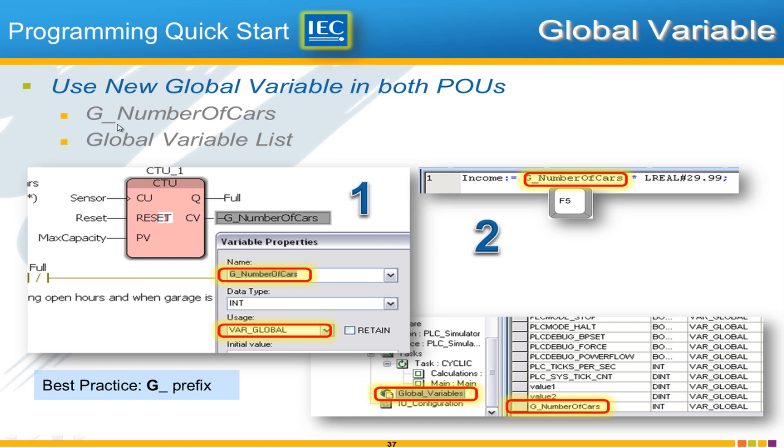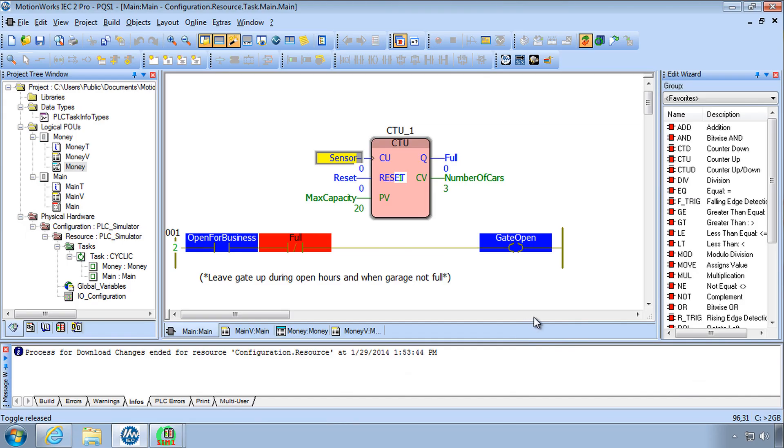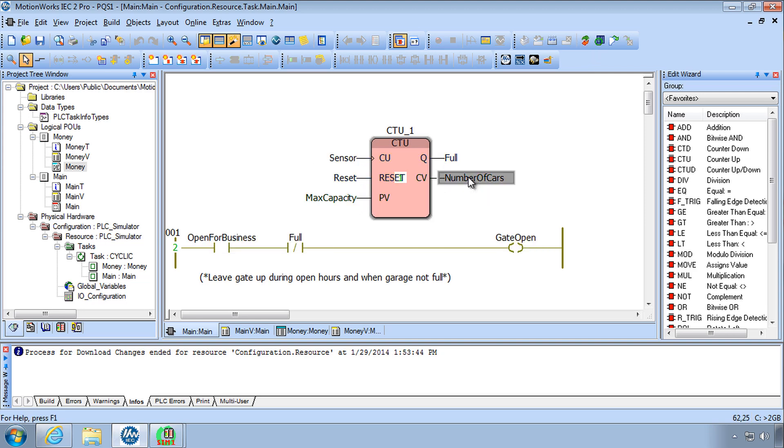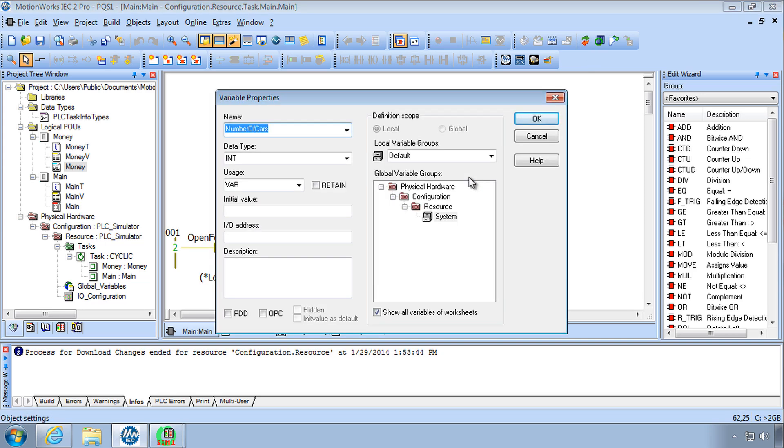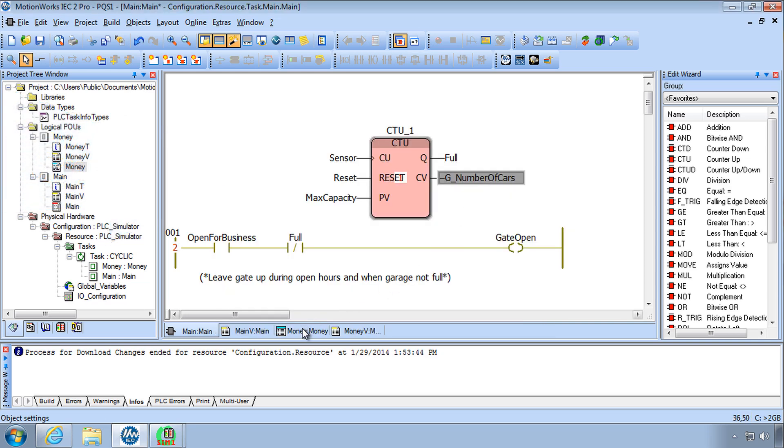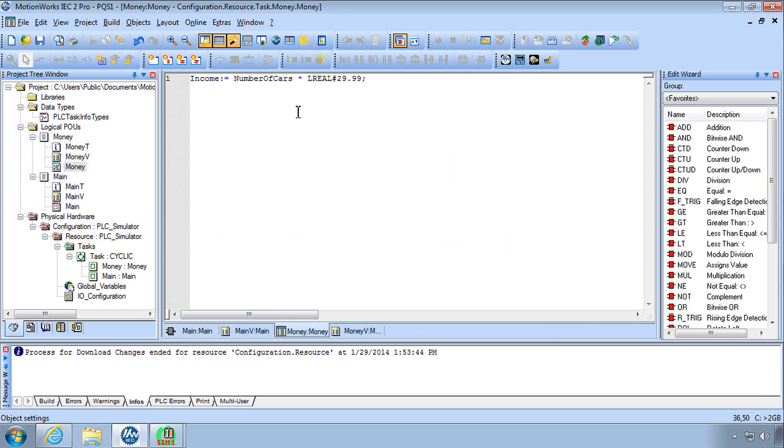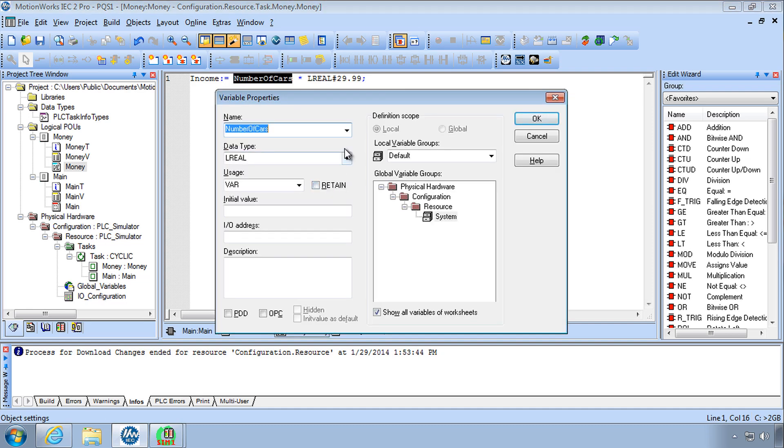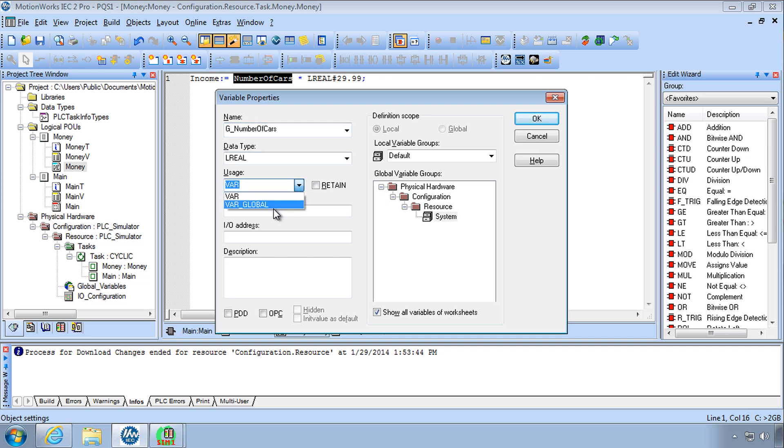So what we need to do is to connect the two POUs to be able to share the data in this variable by using a global variable. And one convention that we have is to make that very clear by putting a G underscore in the name. It's a naming convention for variables. And then you choose var global when you create the variable, and that confirms the fact that you're using a global variable. So global variable allows data to be passed between different POUs. So let's implement this. I'll change my counter from number of cars and I'll put in a new variable called G underscore number of cars.